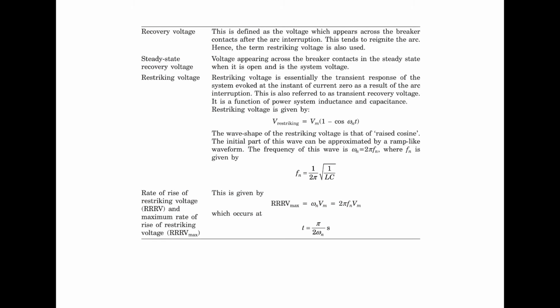Now some of the terminologies that we discussed. The recovery voltage is defined as the voltage which appears across the breaker contacts after the arc interruption. This tends to reignite the arc, and hence the term restriking voltage is also used. Steady state recovery voltage is the voltage appearing across the breaker contacts in the steady state when it is open, and it is the system voltage. Then we have the restriking voltage, which is essentially the transient response of the system evoked at the instant of current zero as a result of arc interruption. This is also referred to as the transient recovery voltage. It is a function of power system inductance and capacitance. This restriking voltage is given by the expression that we have discussed.